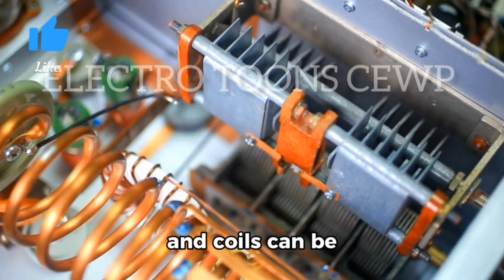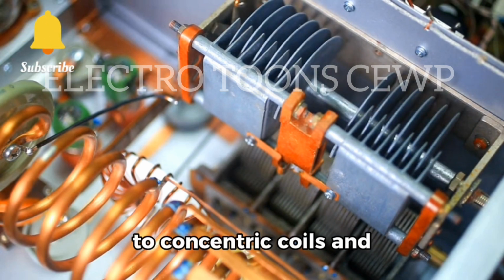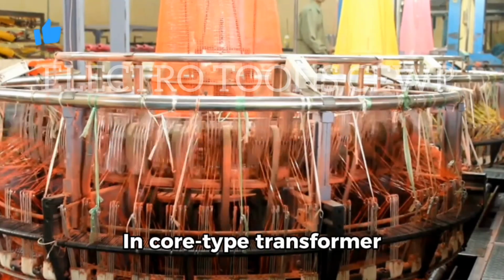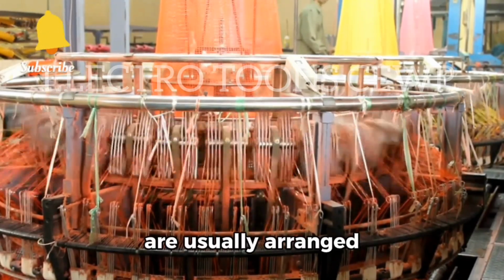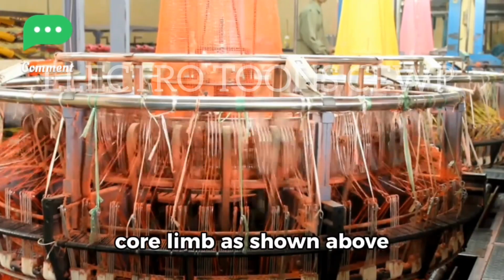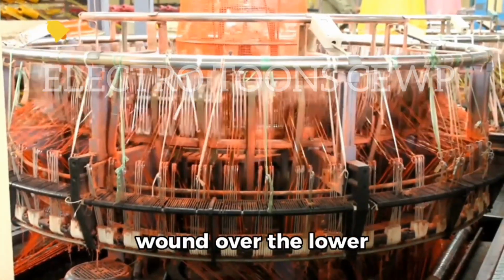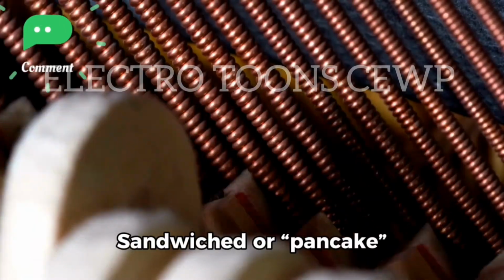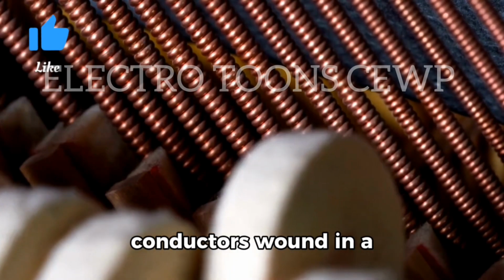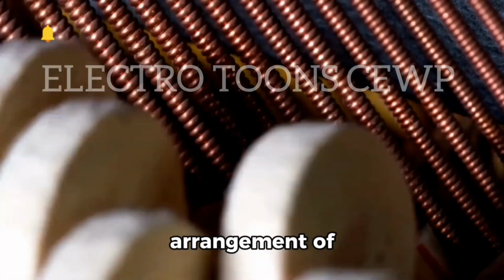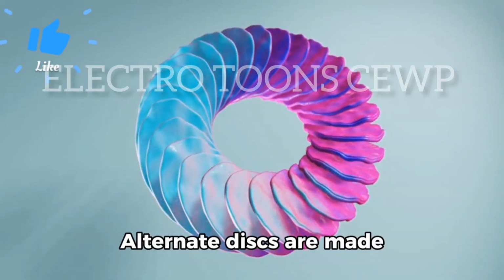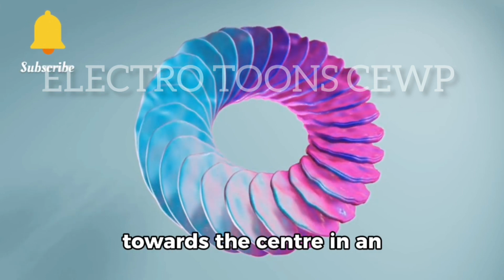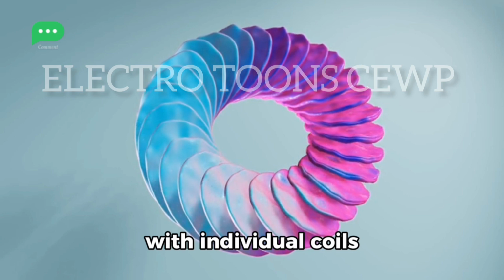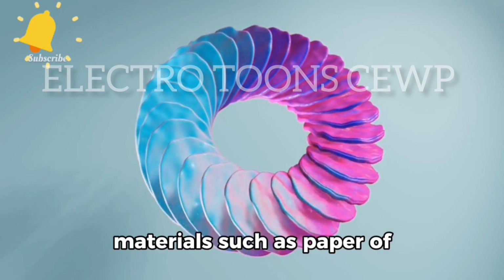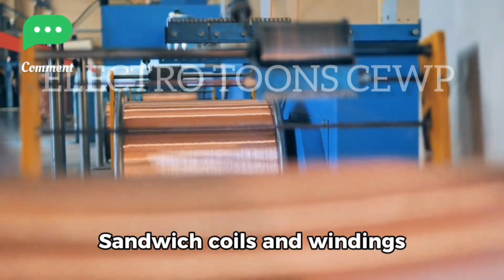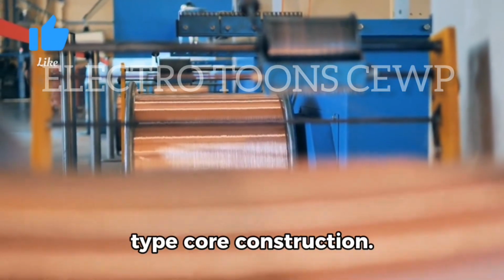Transformer windings and coils can be broadly classified into concentric coils and sandwich coils. In core-type transformer construction, the windings are usually arranged concentrically around the core limb as shown above, with the higher voltage primary winding being wound over the lower voltage secondary winding. Sandwich or pancake coils consist of flat conductors wound in a spiral form and are so named due to the arrangement of conductors into discs. Alternate discs are made to spiral from outside towards the center in an interleaved arrangement, with individual coils being stacked together and separated by insulating materials such as paper or plastic sheet. Sandwich coils and windings are more common with shell-type core construction.